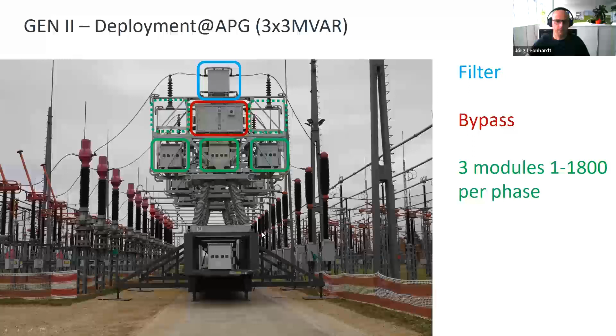These are the 3 green marked modules, and the bypass is the module marked in red. On top of it, you have a filter. With this device, we could switch power in an amount of 20 megawatts, which seems a little bit—I always say homeopathic—in the TSO grid, but it was enough for our proof of concept and our tests.